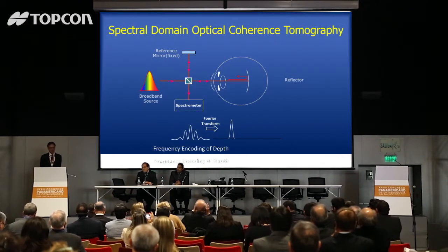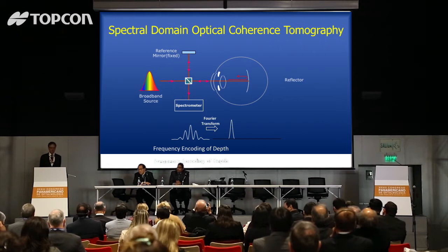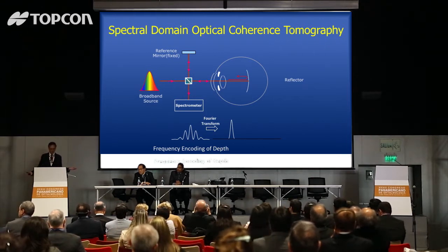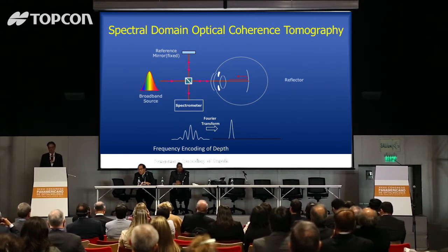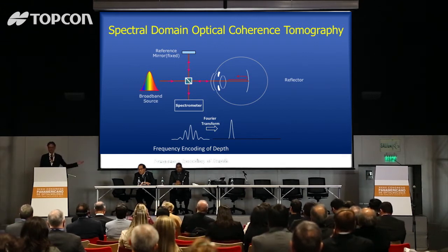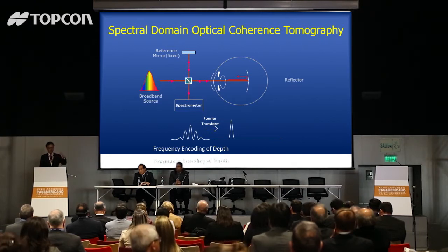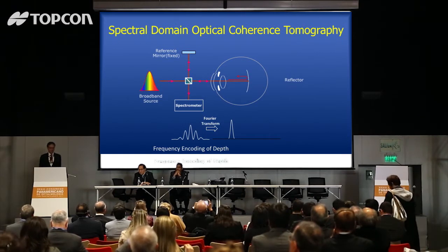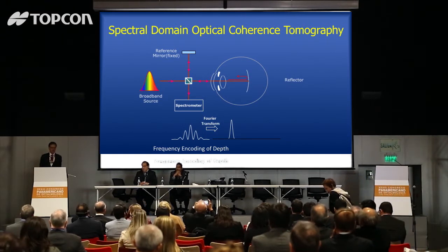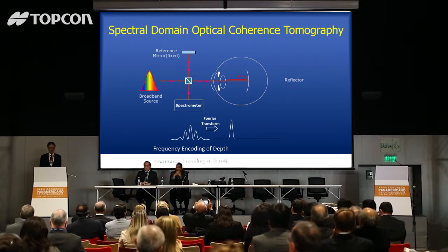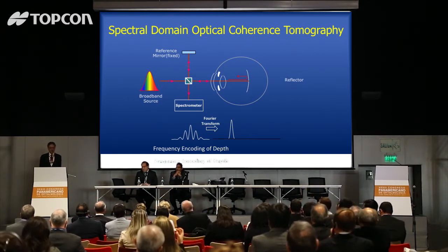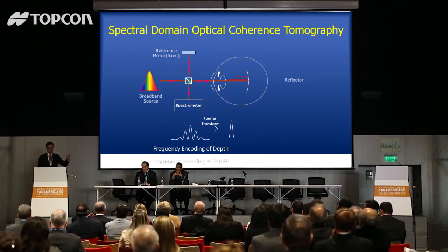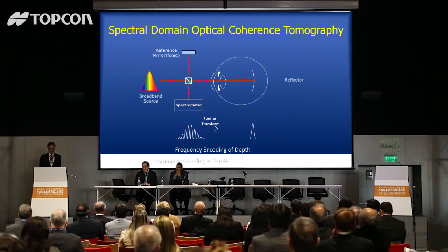With spectral domain OCT, the light source is fairly broadband. It sends a bucket full of wavelengths into the eye. Part of the light is split by a beam splitter to go to a reference arm, and part goes into the eye. Depending on what reflects in the eye, you get a certain amount of reflection back. Those are combined with the light from the reference arm and you get an interferogram.